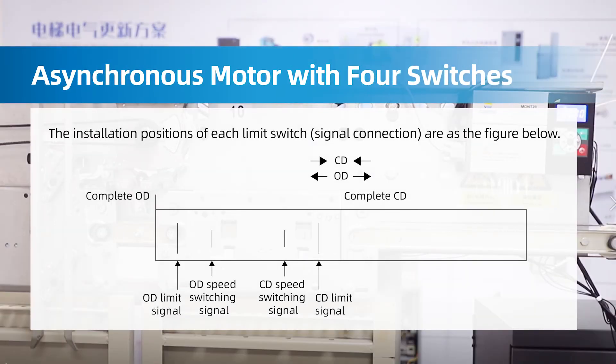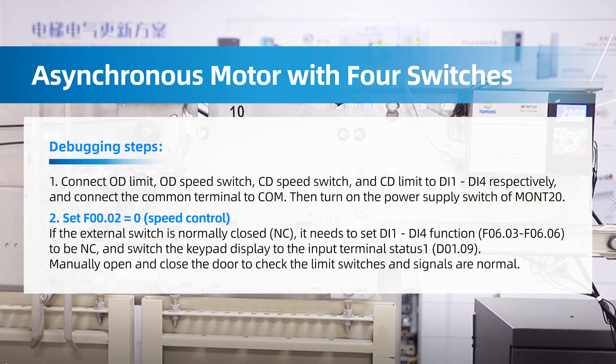Asynchronous motor with four switches: the installation positions of each limit switch and signal connections are as shown in the figure. Debugging step 1: Connect OD limit, OD speed switch, CD speed switch, and CD limit to DI1 through DI4 respectively, and connect the common terminal to COM. Then turn on the power supply switch of MONT20.